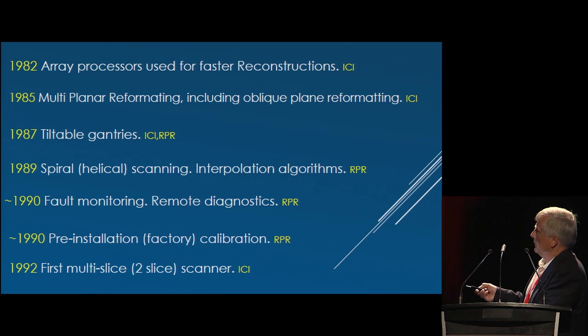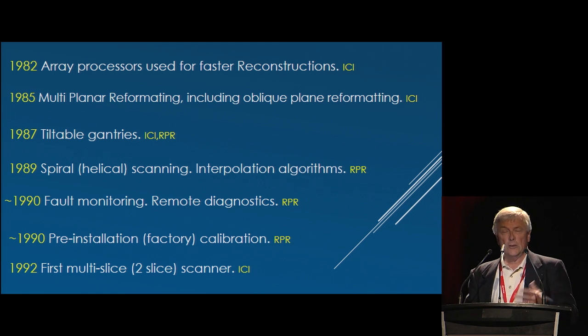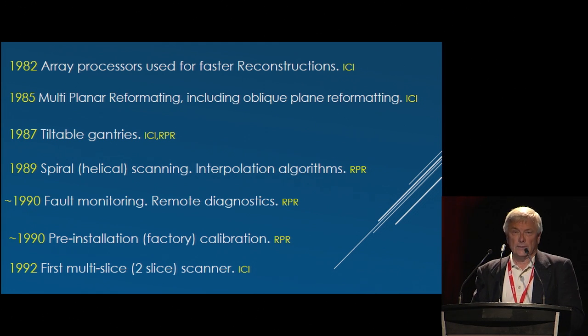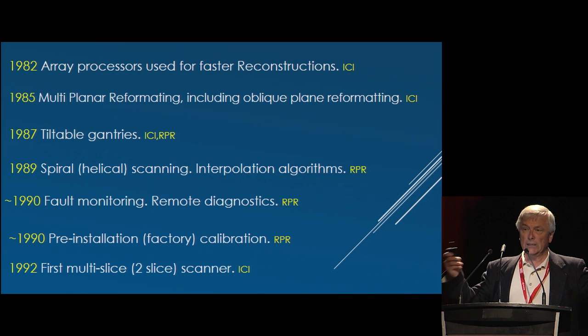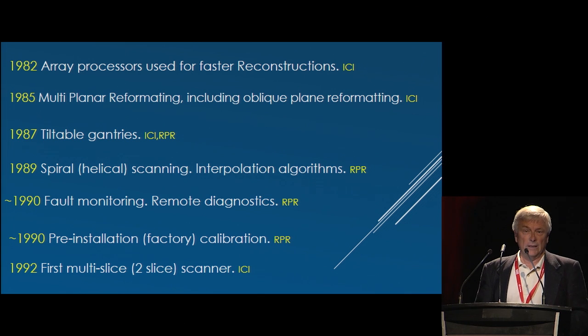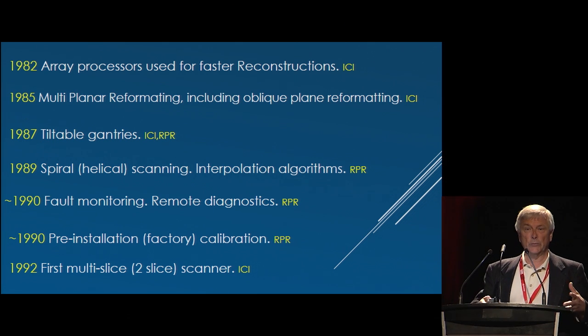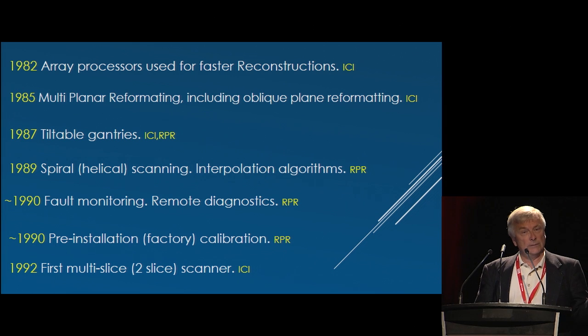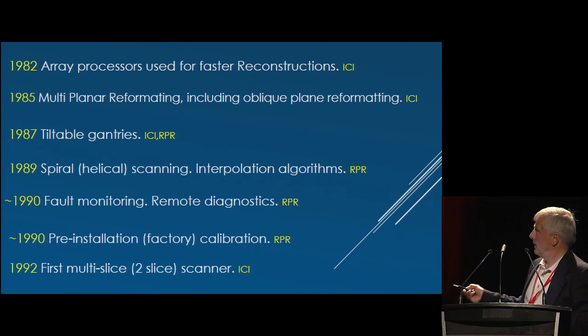And today what's taken for granted is pre-installation factory calibration. Back in the early 90s, the components were brought in to the location, and the on-site field service engineers spent 2 to 3 weeks setting up the scanners, calibrating it, making sure it worked. Nowadays, you can put up a CT scanner literally in about a day or two, and that's because of these little advances.